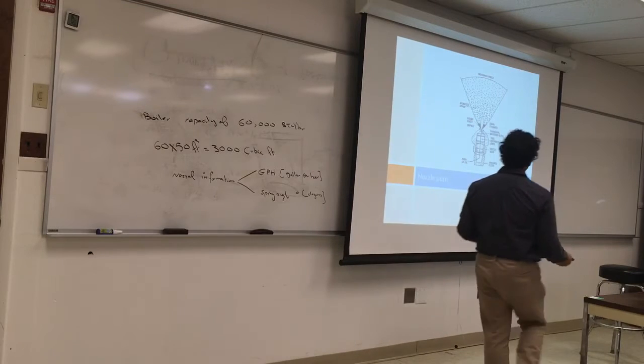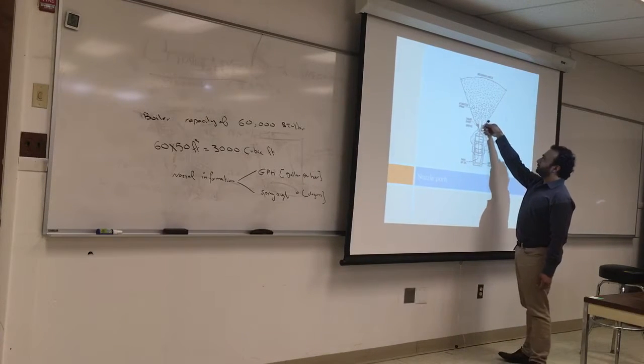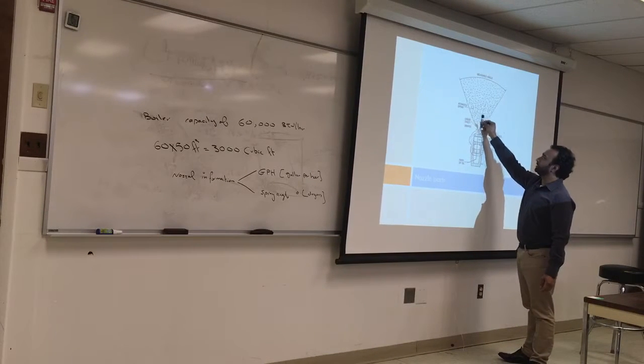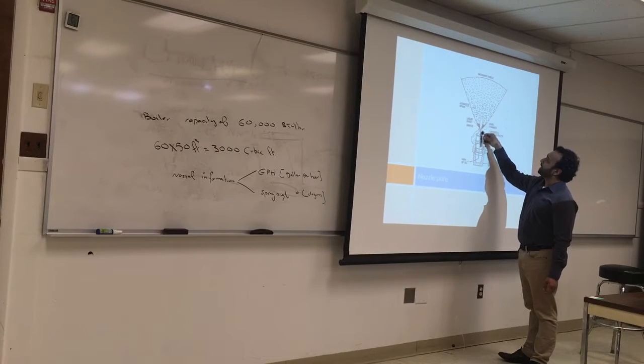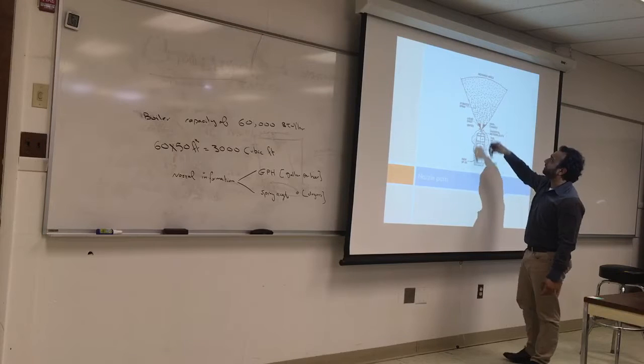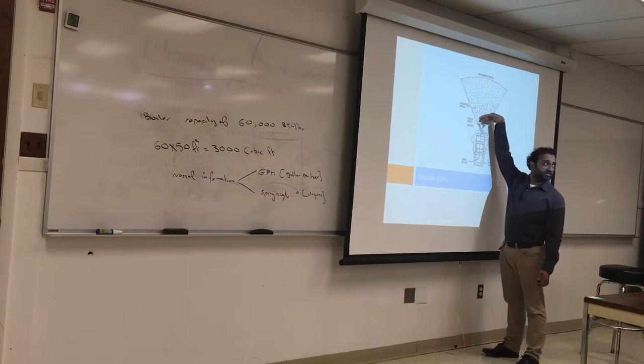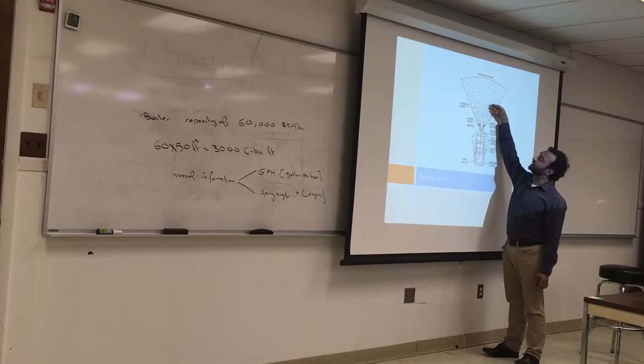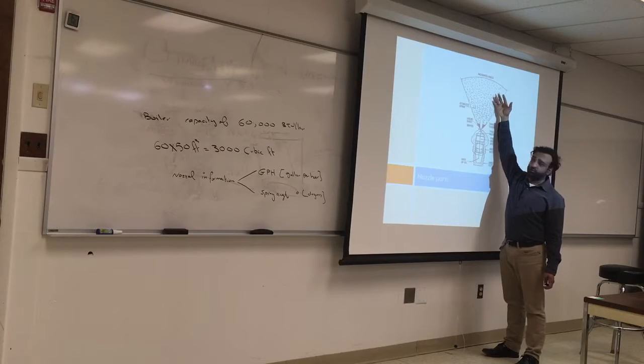The spray angle is measured from one edge of the spray to the other. So this is around 90, probably it's an 85-degree angle. And the flow rate is how much oil is spraying from the nozzle. So this is the atomization, and you can see the density and the concentration of the droplets get less and less as we go further.